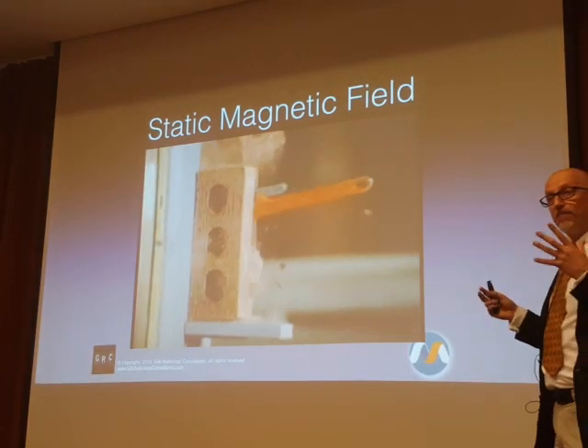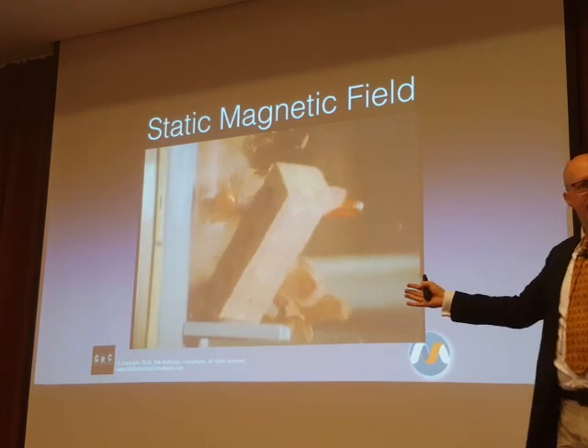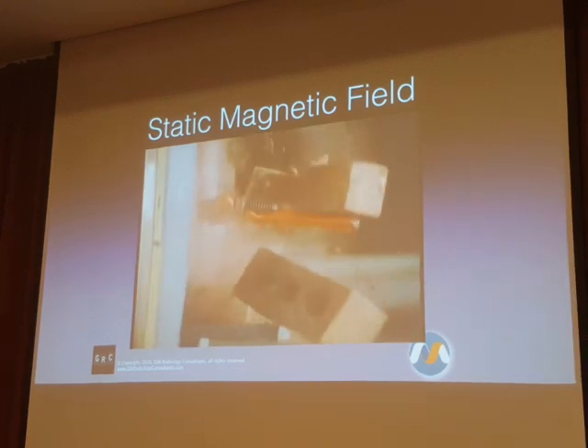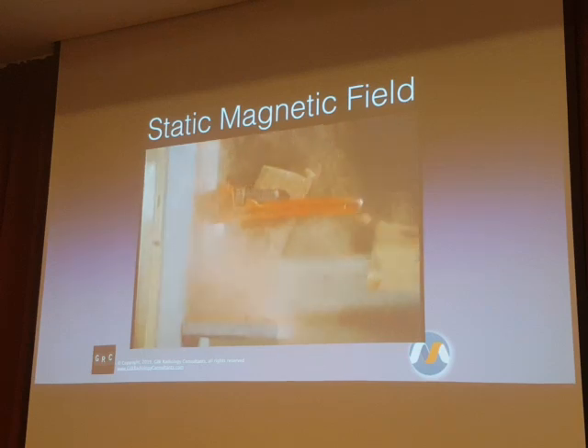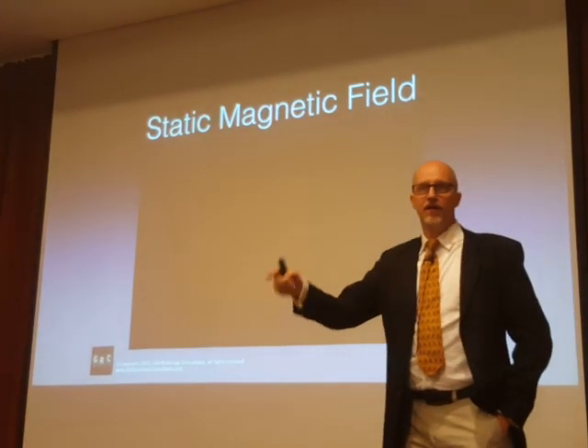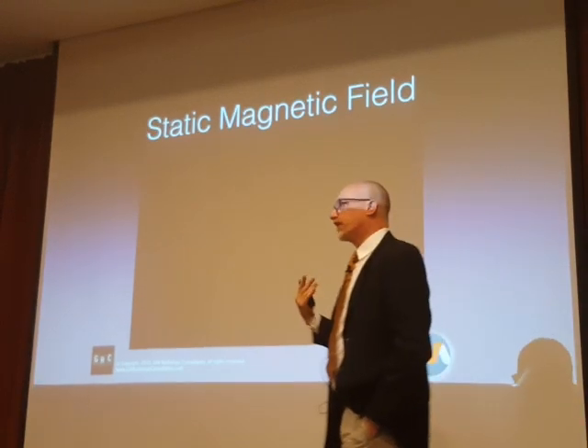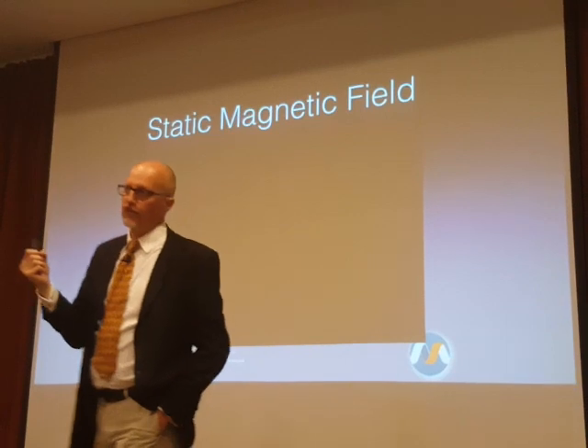As active shielding has gotten better on these magnets, what that means is that the spatial gradient, the part that really drives translational force, gets higher and higher and higher, which means the speed with which something will fly keeps getting higher and higher. It also means that there is less feedback time. It used to be, when they made that video, that if the magnet was over that direction and I had something ferromagnetic in my hand, as I started walking towards that magnet, I would feel nothing. I would feel a little bit of pull. Oh, now it's really pulling. Oh, now I have to hold onto it with 2 hands.